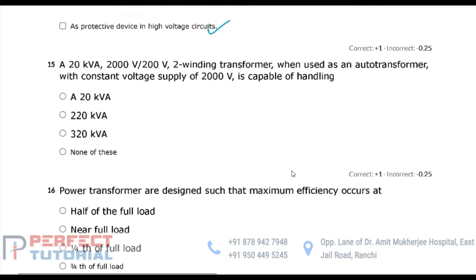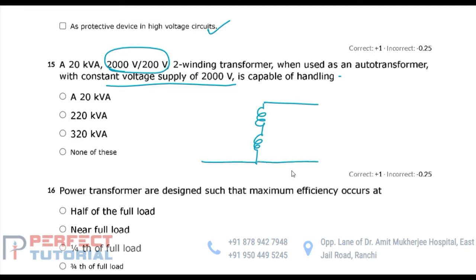Okay, next सवाल है a 20 kVA 2000 by 200 volt two winding transformer when used as an auto transformer with constant voltage supply of 2000 volt it is capable of handling. टू वाइंडिंग ट्रांसफार्मर को रिकनेक्ट किया गया है ऑटो ट्रांसफार्मर कनेक्शन के लिए जिसका सप्लाई वोल्टेज 2000 वोल्ट होना है, एंड ये सवाल पूछ रहा है इट इज कैपेबल ऑफ हैंडलिंग. देखिए ऑटो ट्रांसफार्मर जब भी रियलाइज किया जाएगा टू वाइंडिंग ट्रांसफार्मर से, दो बात ध्यान रखेंगे, until it is mentioned you should consider that the two windings of the transformer are to be connected in series additive connection, and second one is HV winding of the two winding transformer should be taken as common winding. So टू वाइंडिंग ट्रांसफार्मर का जो HV वाइंडिंग होगा वो कॉमन वाइंडिंग होगा, एंड जो दोनों वाइंडिंग का कनेक्शन होगा इट वुड बी इन सच ए मैनर सो दैट दे आर इन सीरीज additive polarity.